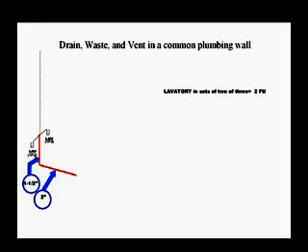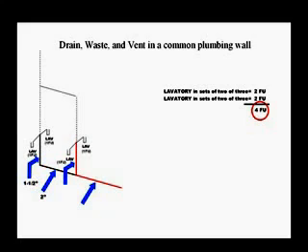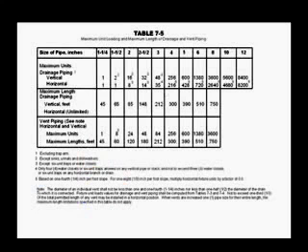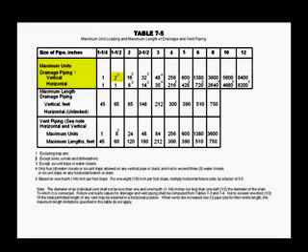Let's add an additional bathroom with double lavatories, which increases the fixture unit load to 4 for the horizontal drain. Refer to table 7-5, then under Maximum Units Vertical, 2 fixture units fits under 2 fixture units, which will require a 1-1/2 inch vertical drain. And under Maximum Units Horizontal, 4 fixture units fits under 8 fixture units, which will require a 2 inch drain.